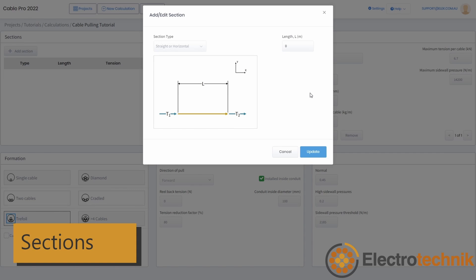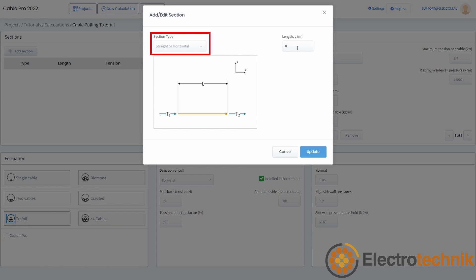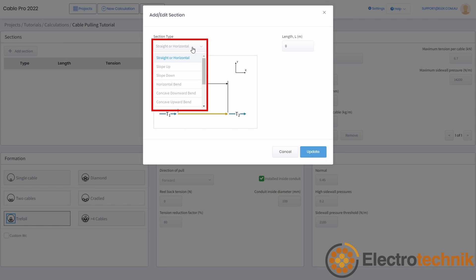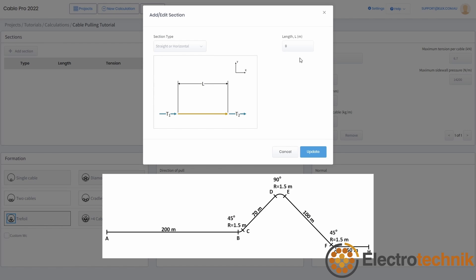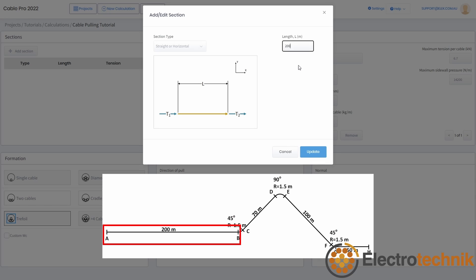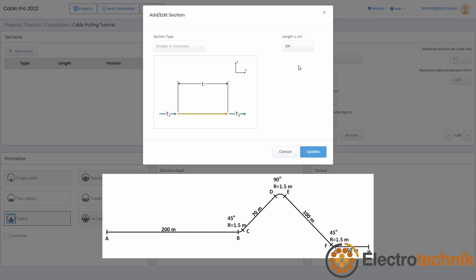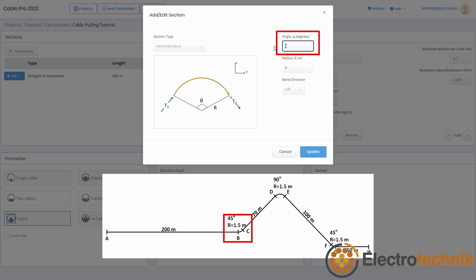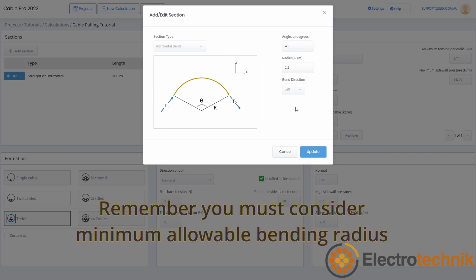When you open a new calculation, the add section window will appear. You should select the section type from the dropdown menu which matches your first section from your layout drawing. Enter data in the popup window based on the section type selected, such as length, and for a horizontal bend, the angle or bend radius. Note that when you enter a radius, you must consider the minimum allowable bending radius of the cable.